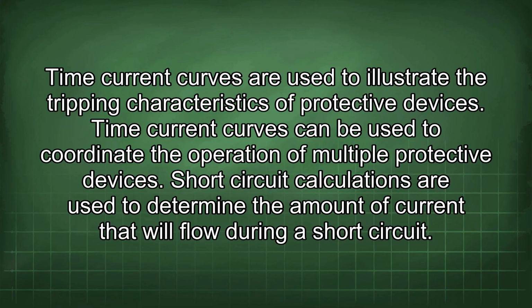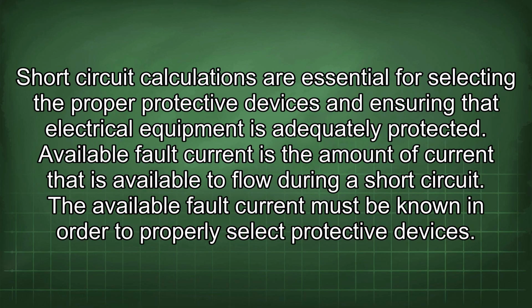Short circuit calculations are used to determine the amount of current that will flow during a short circuit. Short circuit calculations are essential for selecting the proper protective devices and ensuring that electrical equipment is adequately protected. Available fault current is the amount of current that is available to flow during a short circuit.